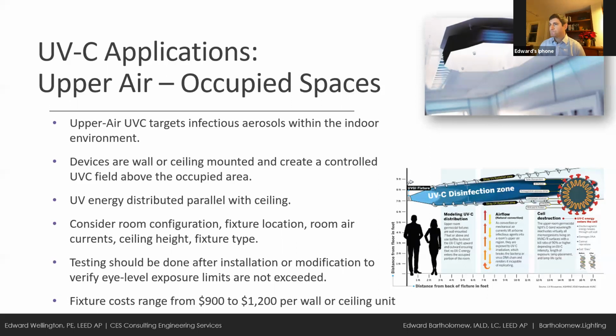It's worth noting testing should be done in the commissioning process, with meters, to ensure that eye level exposure limits are not exceeded. You can put warning signs on the wall as well if suggested. And the economics really favor the in-duct approach, but we're oftentimes dealing with existing school buildings that may or may not have full ducted HVAC systems.